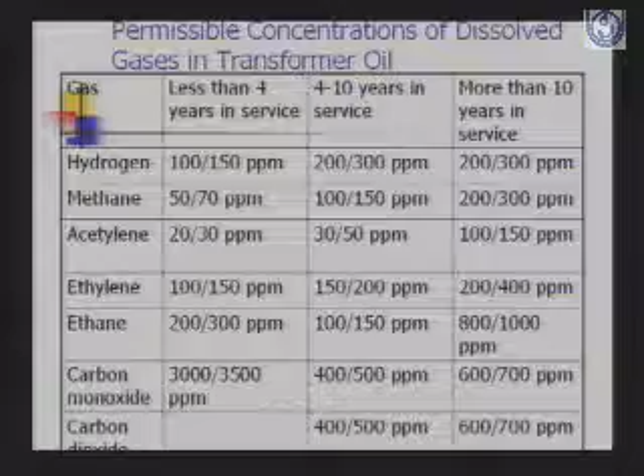If it is less than 4 years in service, then for example the concentration of hydrogen should be less than 100 to 150 ppm. If it has been 4 to 10 years in service, then its concentration should be less than 200 to 300 ppm. If it has been more than 10 years in service, then its concentration should again be less than 200 to 300 ppm. So these are the various values of dissolved gas in the oil which can give you an indication of the condition of the transformer oil. If the concentrations are more than this, then action needs to be taken.